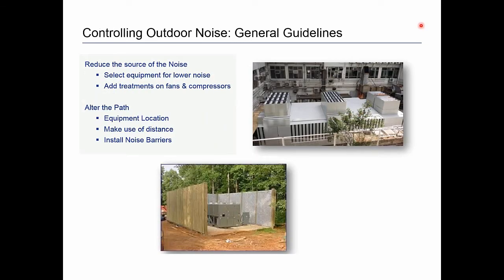To control outdoor noise from your units, you have the same two choices as anywhere in noise control: reduce the source by selecting inherently quieter equipment or adding treatments to fans and compressors, or alter the path of the sound. You can change the equipment's location, make use of distance — remember, sound decays with distance — and most commonly, install noise barriers around the unit. Barriers can be very effective, but they have to be planned and executed correctly, and they're not always as cost-effective per dollar spent as you might hope.